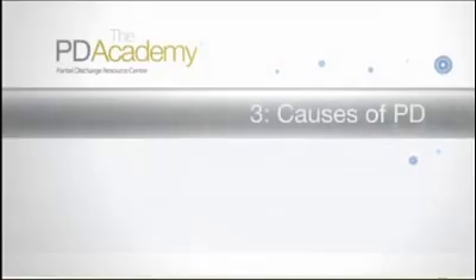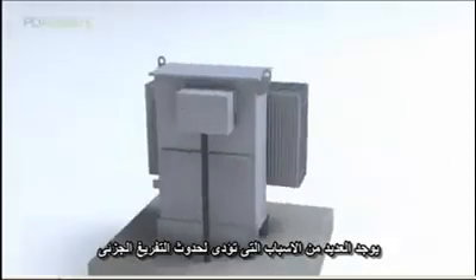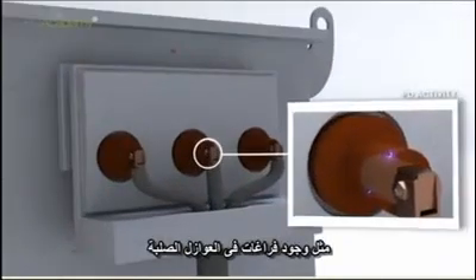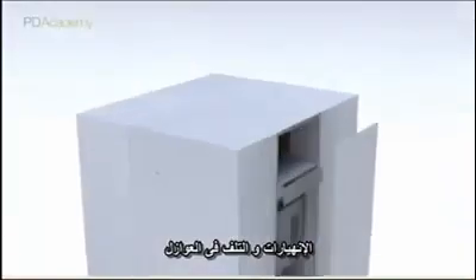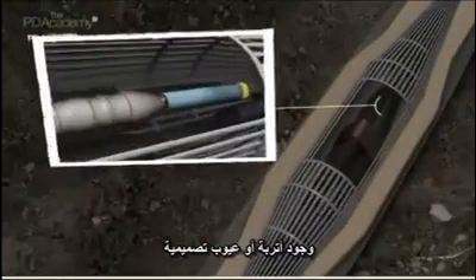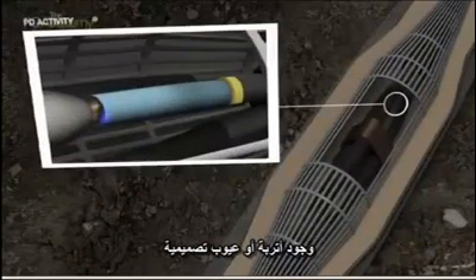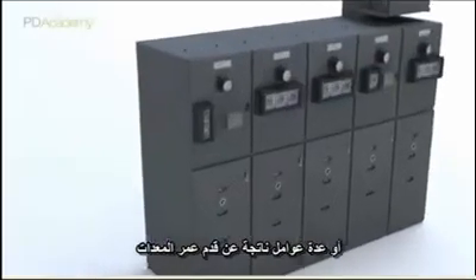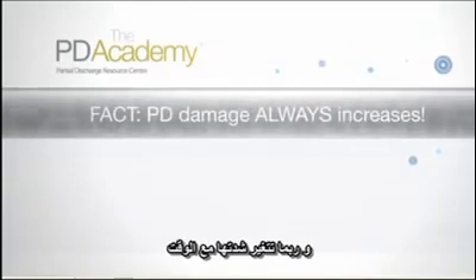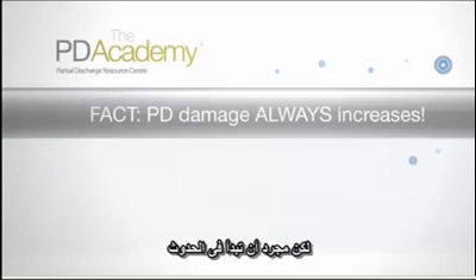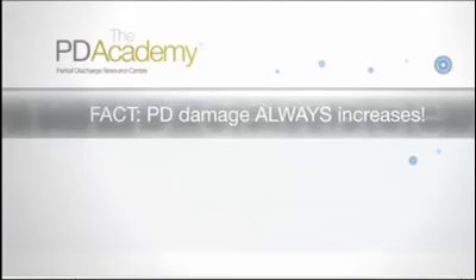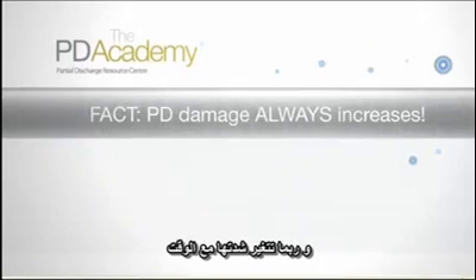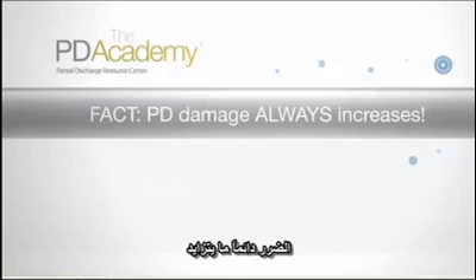Causes of PD. Partial discharge activity has many causes, including voids in solid insulation, often caused during manufacture, mechanical breakdown or damage to insulation, sometimes caused during installation, particle contamination, design defects such as poor stress control, or irregularities, or a combination of factors that are characteristic of assets getting old and ultimately breaking down. PD activity may be intermittent, or it may vary in intensity over time, but once it starts, the damage always increases.